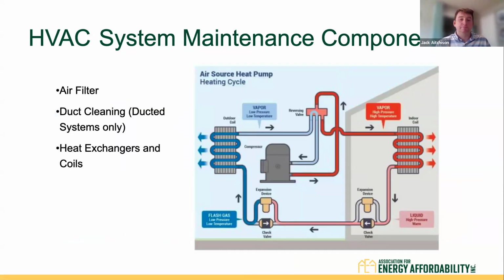Next slide. So items that you need to maintain in heat pump HVAC. Starting off with air filters, you're going to have an air filter on the indoor coil. That is filtering the air that is returning back to the coil to be reconditioned and sent back out to the dwelling unit. That can be through ductwork. That can be through a single head unit if you have a mini split system. But you have an air filter that needs to be cleaned. If you don't clean it, you could run the risk of reducing the airflow over the indoor coil, which is going to reduce the efficiency. You can also start to get gunk on the actual coils themselves.